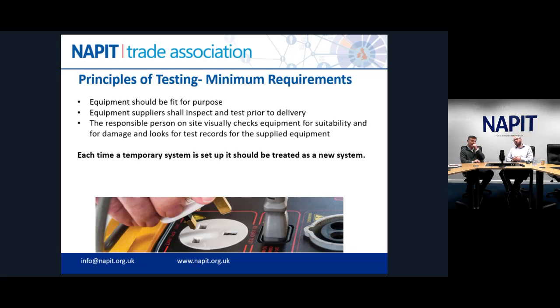Okay, so as we've said there, each time it's set up, it should be treated as a new system. Yes, and this can be a bit of a problem, particularly on tours where we might be going from venue to venue. Technically, although it's the same kit, it's the same hardware, and it's the same distribution, every time you go to a new venue, it's classified as a new installation. And there are reasons for it, not least that at each different venue, the characteristics of the supply are going to be different. So where I might have a socket on the wall that I connect my distribution to, in one venue, the earth loop impedance might be quite low, the next venue could be quite high. So it's important to make sure that the system is checked to make sure the protection is going to work at each different venue.